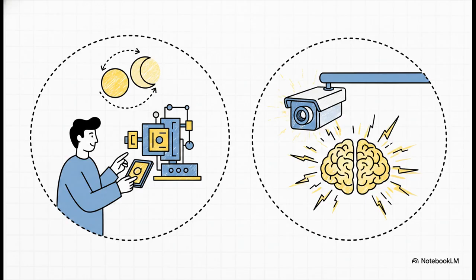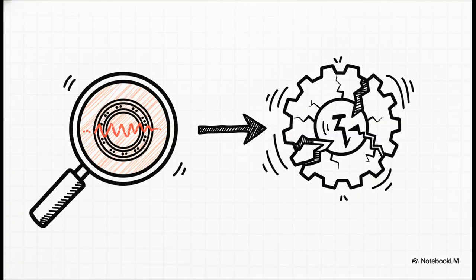But continuous AI thermal monitoring completely shatters that outdated assumption. It shifts detection from a reactive once-a-month check to a proactive, real-time prevention strategy. Here's the mechanical truth of how AI thermal catches failure so early. A modern system measures temperatures 25 times per second. That's lightning fast. And it's analyzing every single pixel against a massive database of historical baselines for that specific machine. It's not waiting for a bearing to hit 200 degrees. It instantly detects a tiny 5-degree deviation.